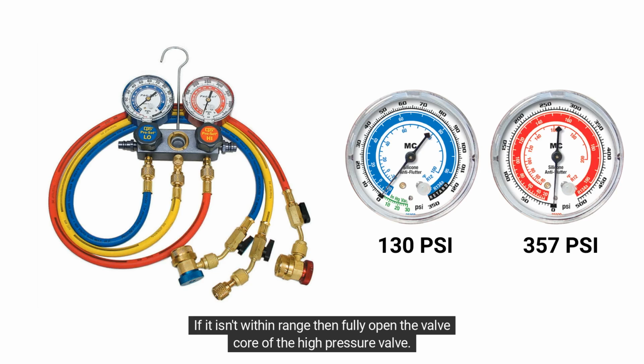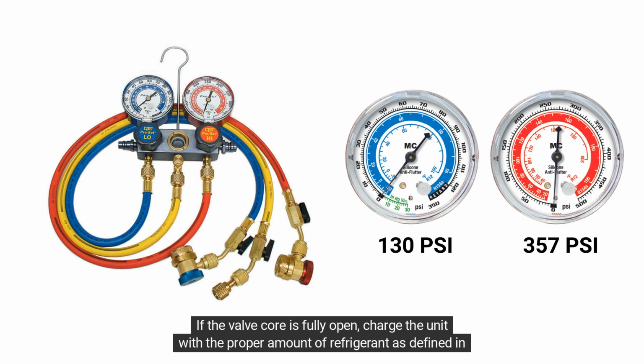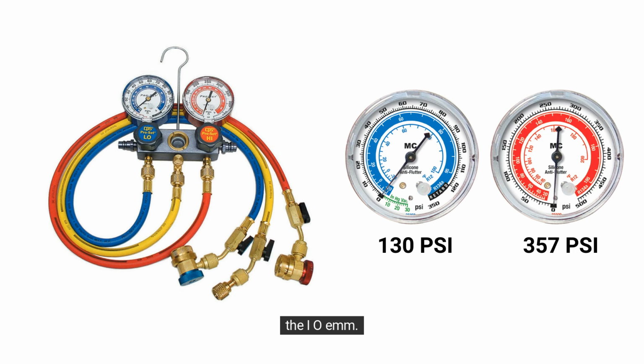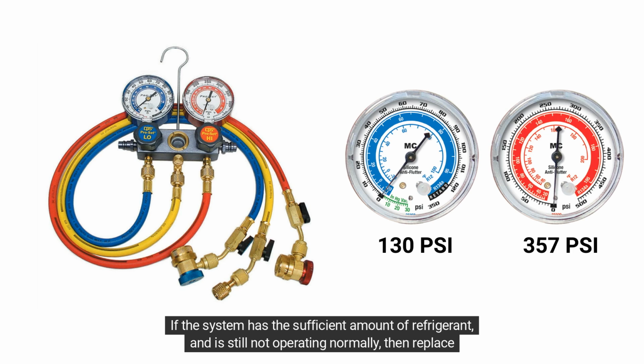If it isn't within range, then fully open the valve core of the high-pressure valve. If the valve core is fully open, charge the unit with the proper amount of refrigerant as defined in the IOM. If the system has the sufficient amount of refrigerant and is still not operating normally, then replace the PCB.